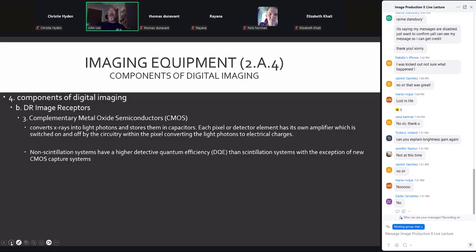The complementary metal oxide semiconductors, or CMOS systems, convert X-rays into light and store them in capacitors. So they work along the same principles as the two separate components with the scintillator and the CCD, but all of it is contained within this one device. It's got its own detector, its own amplifier. They're switched on and off, that allows for converting those electrons and light photons to electrical charges. Your non-scintillation systems, in other words, systems that don't require conversion of X-rays to light, have a higher detective quantum efficiency than those that require the scintillator, which means they actually require less radiation to use. The only exception to that is a few of the CMOS capture systems.